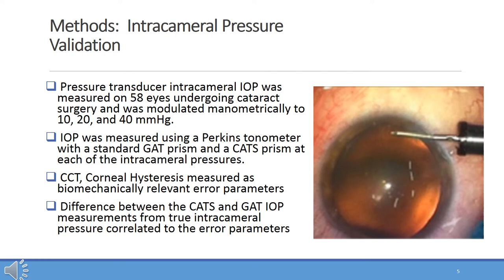The methods center around validating the findings in mathematical modeling and clinical testing. Since comparing intraocular pressure measurements to the Goldman as a reference does not say anything about improved accuracy over the gold standard Goldman, we wanted to compare the CATS and GAT measurements to a true transducer intracameral pressure in live human eyes. We manometrically modulated and measured the intracameral pressure on 58 unique eyes sequentially from 10 to 20 to 40 millimeters of mercury. Simultaneously, we measured the intraocular pressure externally with a Goldman-type Perkins applanation tonometer using both the standard GAT prism and the CATS prism. We then correlated the difference in GAT and CATS IOP measurements from the true intracameral pressure to central corneal thickness and corneal hysteresis measured before surgery.